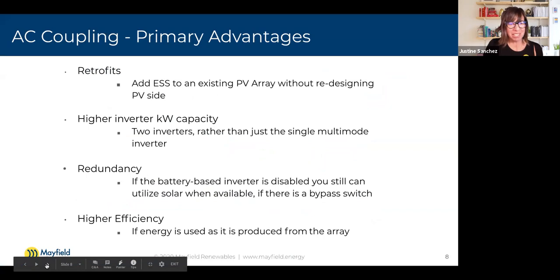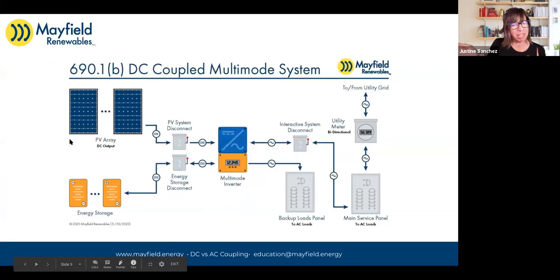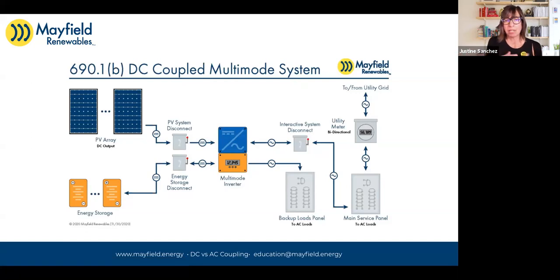So which leads us into this—I'll come back to the pros and cons. This is our DC coupled system. Let's say we're starting fresh, not a retrofit, designing a system from scratch. In that case it would be a lot easier to consider a DC coupled system, because none of this gear is already in place. We don't already have an existing PV array with an interactive inverter installed on the roof. We can step back and ask what options we have, and why we might want to do it this way. So let's talk about a DC coupled system and what that means.